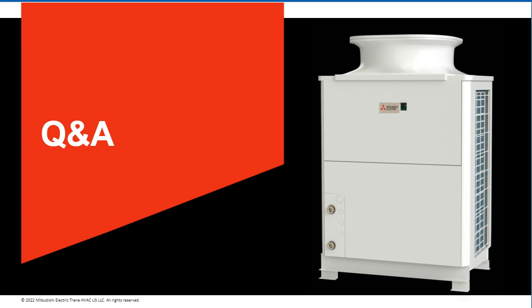Gotcha. All right. Matt, anything you want to add? Just to add to that, the heat exchanger, that spiral tube gas cooler in the heat pump itself, is technically a double wall heat exchanger as well. So we're adding even another layer of protection, but we're really using that secondary heat exchanger for ease of serviceability and ease of cleaning, things like that within the system, for overall longevity of the system.